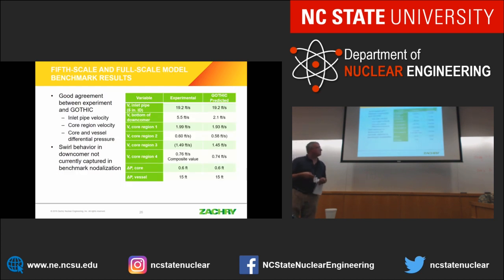And here are the results. As you can see, I matched the inlet pipe. I didn't match the flow at the bottom of the downcomer, and that's because the holes from the inlet volute into the downcomer are at a 30-degree angle, producing a swirl pattern. So that 5.5 feet per second represents the swirl velocity as opposed to the downward velocity. My model only gets the downward.